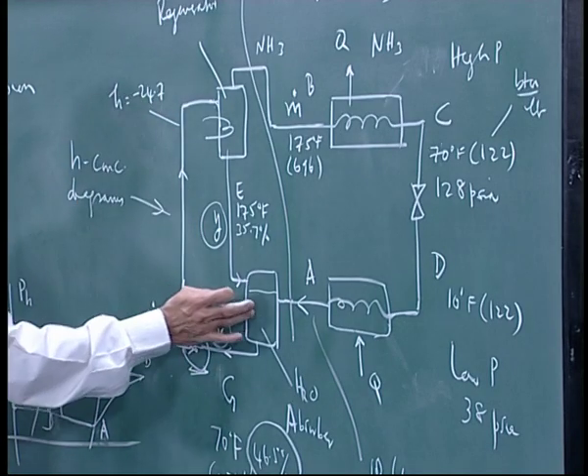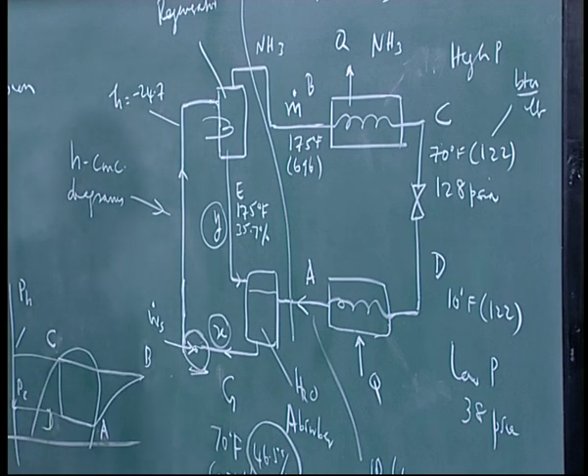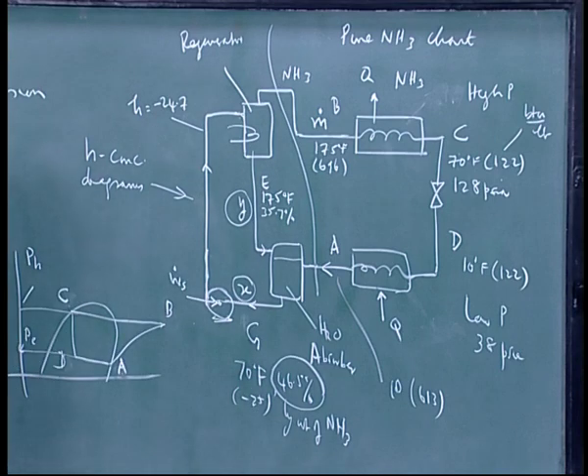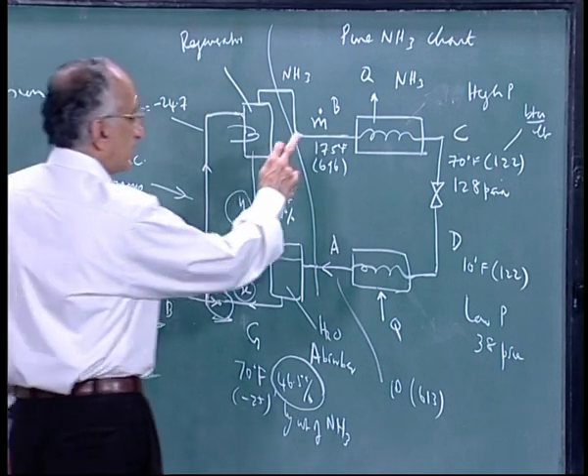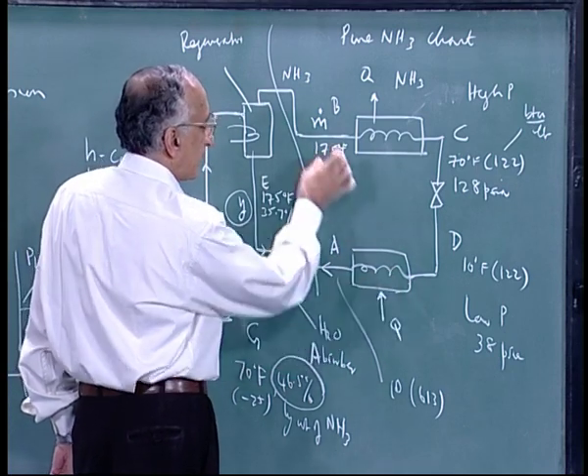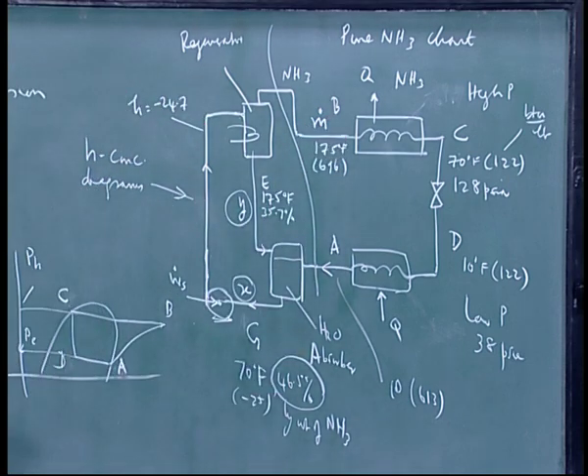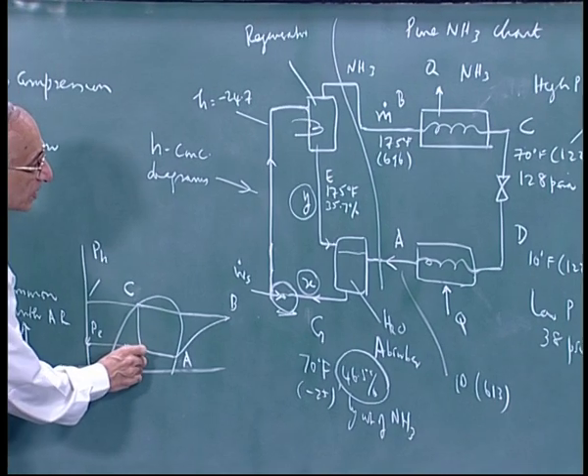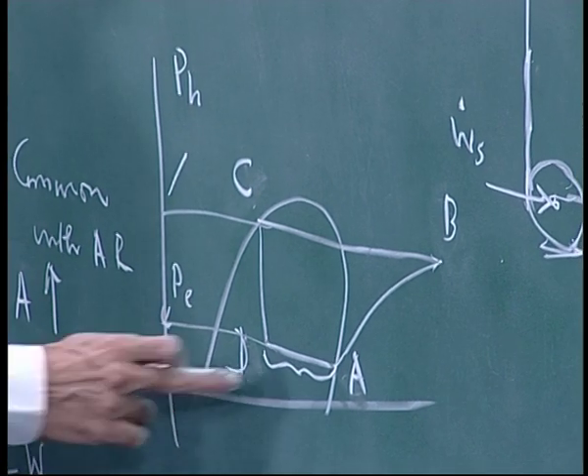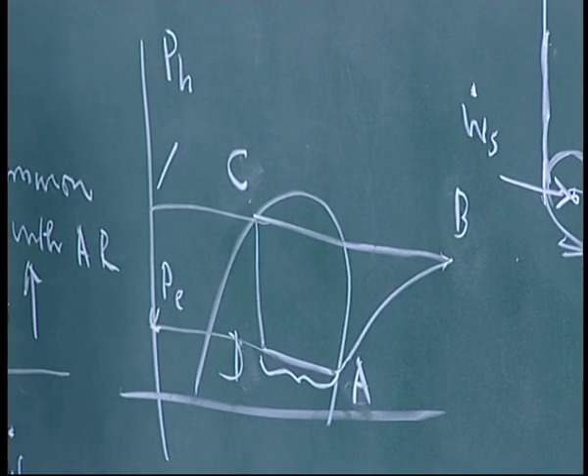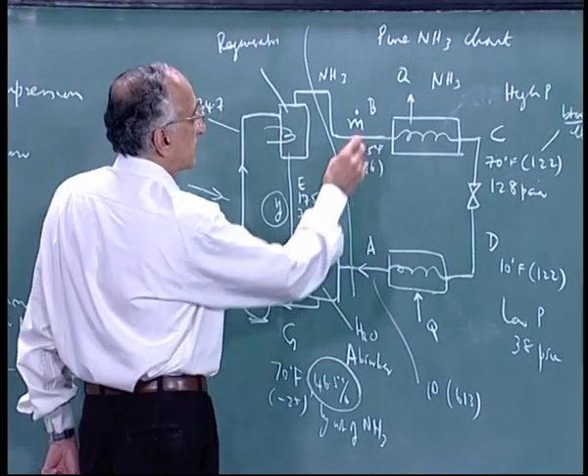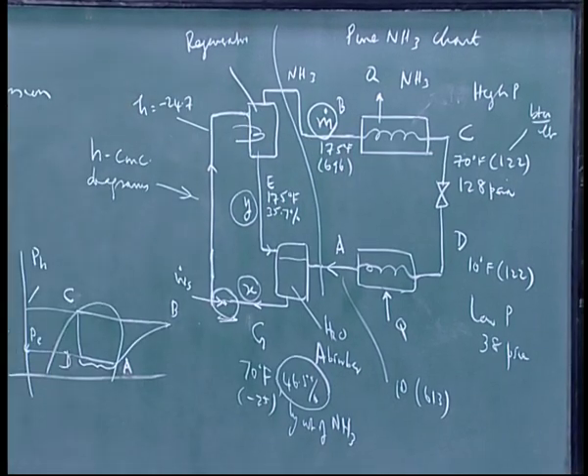You need to design the absorber and regenerator — determining flow rates X (concentrated solution from absorber) and Y (weak solution returning from regenerator). The total refrigeration enthalpy pickup per pound of ammonia is H_A minus H_D from the pure ammonia chart. Your total refrigeration demand divided by this enthalpy difference gives M_dot, which is fixed in the design.